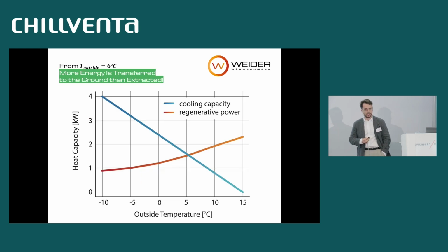So these were our first calculations, how much we can actually regenerate from the heating energy we take from the source. In orange, you see the regenerative power of the geoAir, so how much these two heat exchangers actually can regenerate during the heating period. And the blue line is the cooling capacity, so how much power the heat pump actually takes from the source. You can see that at around 6 degrees Celsius outside temperature, these two lines cross. So whenever it's warmer than 6 degrees outside, we actually regenerate more energy into the source than we take out of it. And when we are, for example, at 0 degrees, we only take out 50% of the energy if no geoAir is used. And this is all during the heating period.